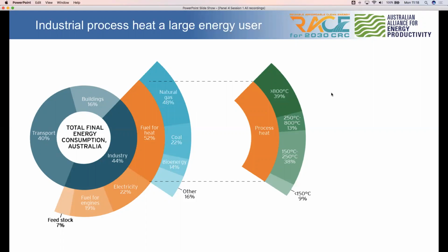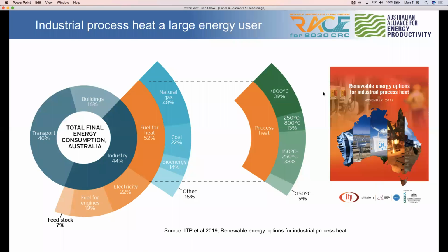If you took that heating demand, or actually the heating production, and broke it into the temperatures it's needed for, you see a very large chunk is at 250 degrees and above, and that's certainly not in the heat pump range. In this bottom 40 or so percent, 250 degrees and below, that is within the heat pump range. Often you'll have a steam boiler producing steam at 10 bar or so, and that would have registered in that 150 to 250 degree range. But that steam may be used just for pasteurization at 80 degrees or so, and so that could definitely be done with a heat pump as well. So we look at something like 30% of process heating that can be done with heat pump technology. There was a very good report done in Australia summarising all this information. I understand some similar things have been done in Europe and the US as well.